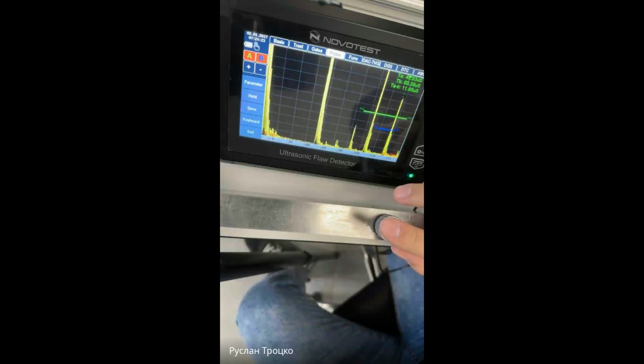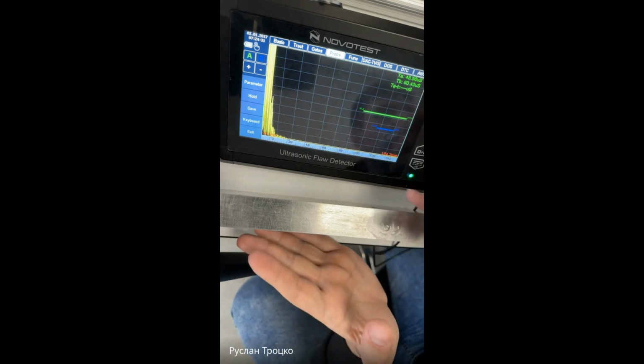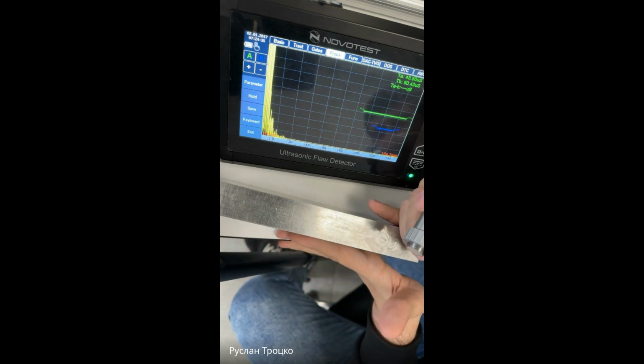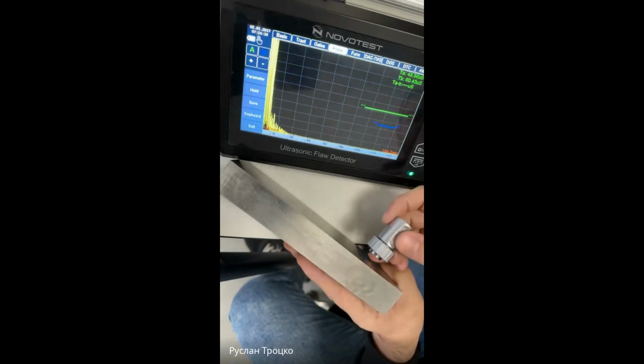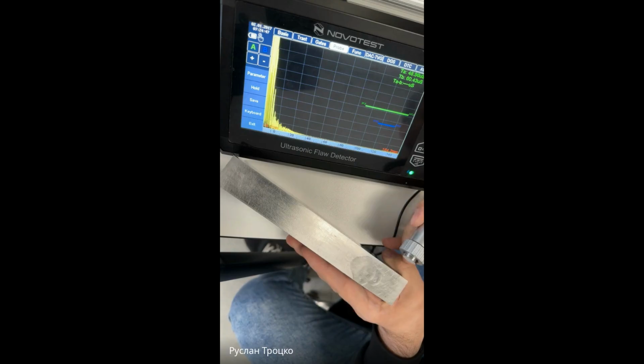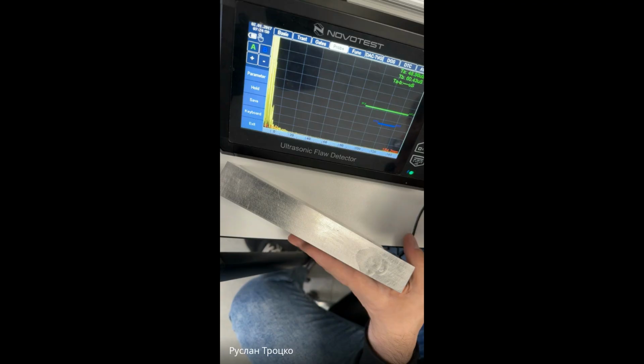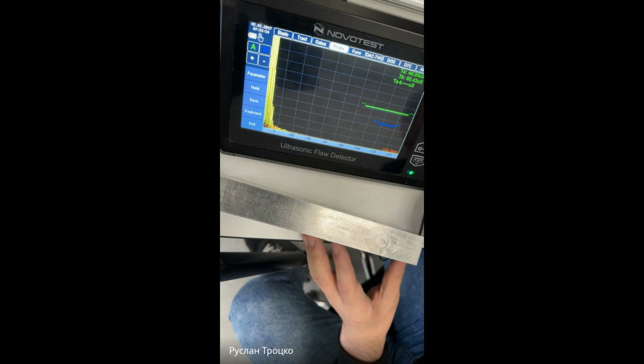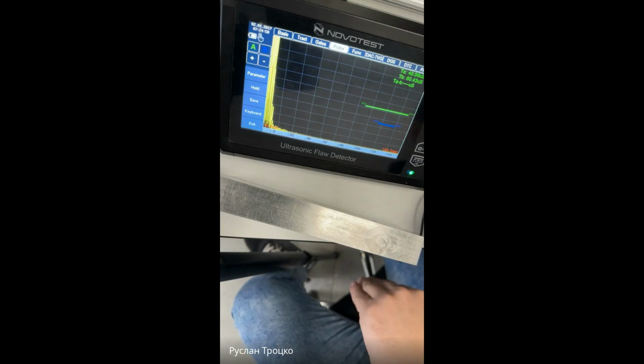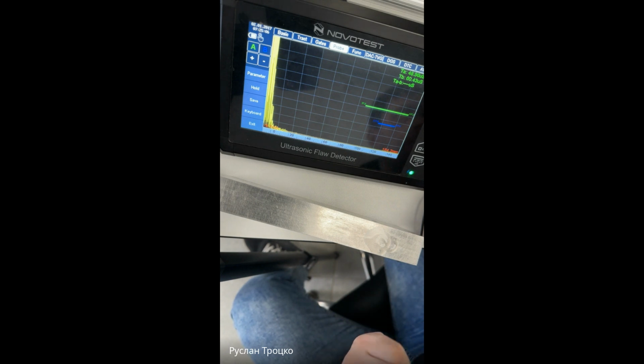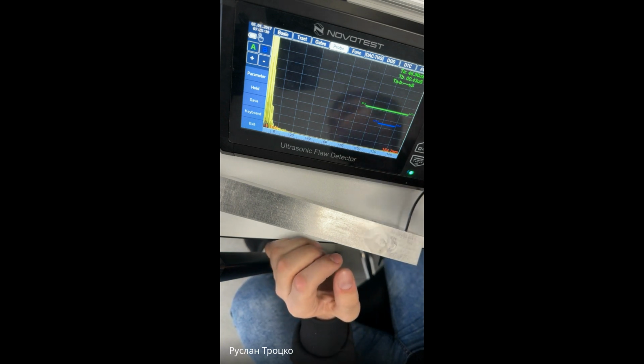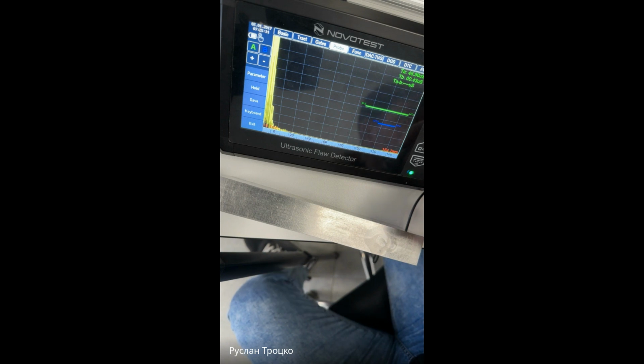Okay. Actually, can you put the probe on the other side of the calibration block? You should put it like this. No. Place it on a flat surface. On a flat surface. Yes, exactly. Yes. Because the ultrasonic beam is coming directly, and then it is reflected from the back wall. And if you put the probe on the other side, it will not be reflected because the back wall is angular.